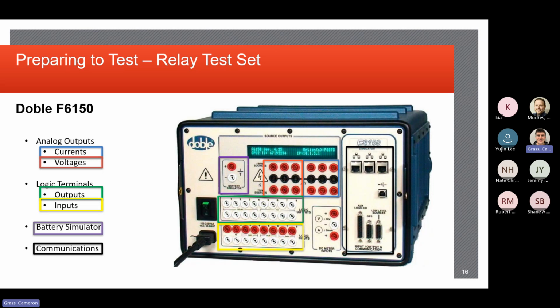So like Brian was talking about, we've done our due diligence. We've looked at everything. This is probably the most common test set. This is probably the only one that I've really ever used when I was out in the field, a Doble F6150. It's pretty common to see this out in the field being utilized for relay testing. What you can see on the red and blue ports are the current and voltage analog outputs that are basically going to be supplied from the test set to the relay when you're doing your testing, to be able to supply current and voltage values to the relay.